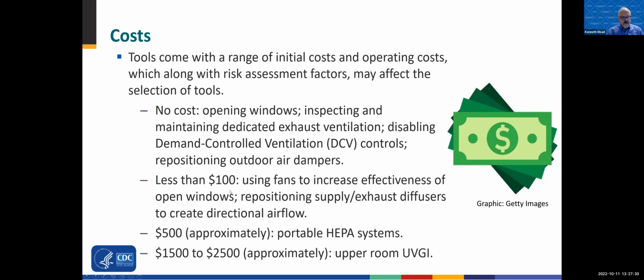Now, if you look at those same units and look at operating costs, obviously there are operating costs with opening windows if it's causing you to have to treat more outdoor air and temper it more, depending on what your ambient environment is. There are energy costs associated with operating fans and HEPA systems, as well as other impacts such as noise that might be generated. UVGI, on the other hand, while it has a higher first cost, its operating cost is actually very low, and you're treating multiple people in a larger space, so your dollar per square foot of clean air, so to speak, becomes cheaper over the long haul.